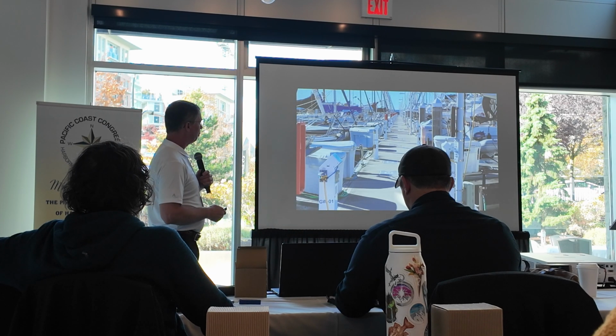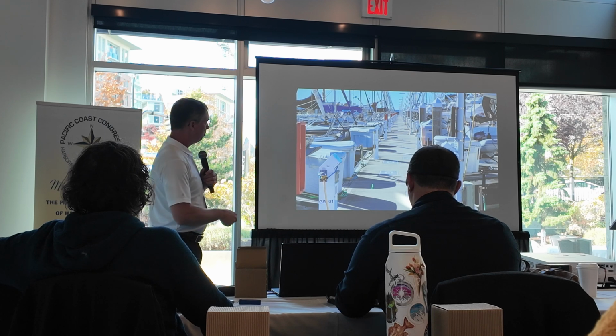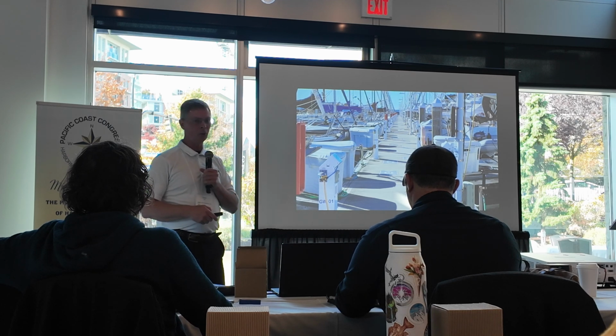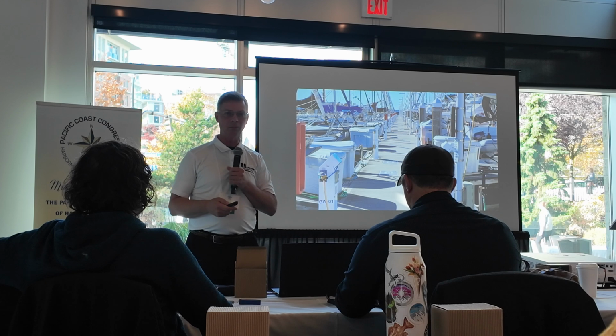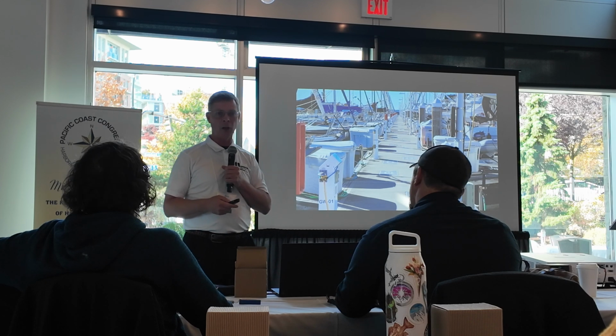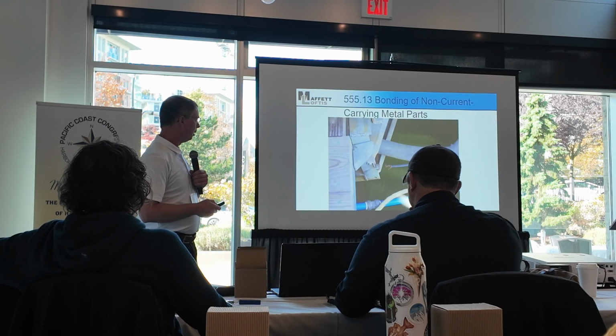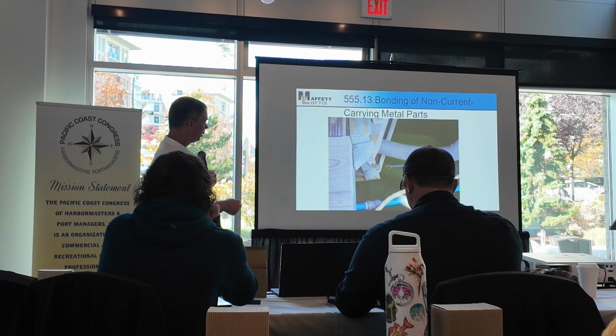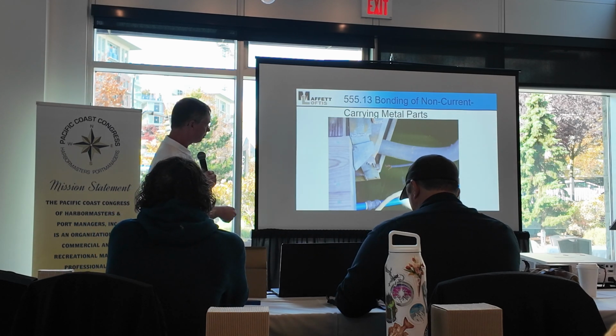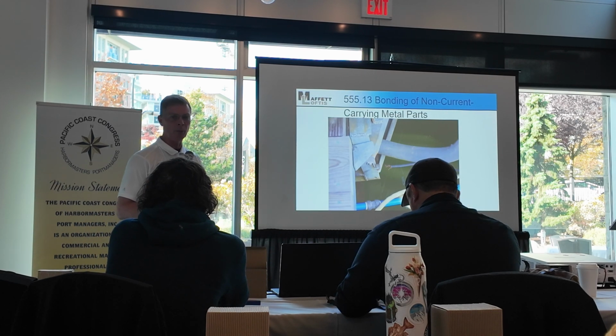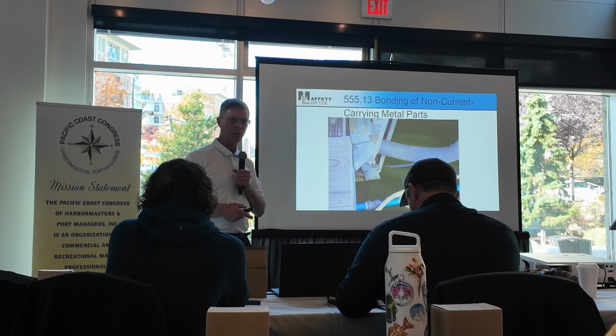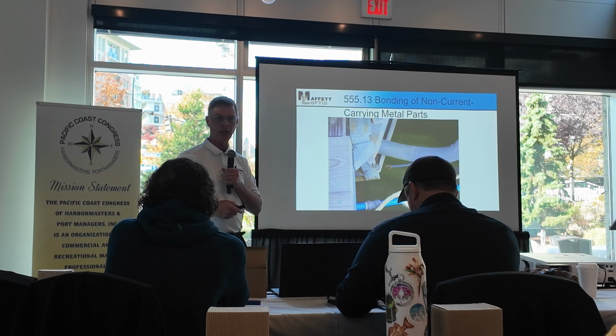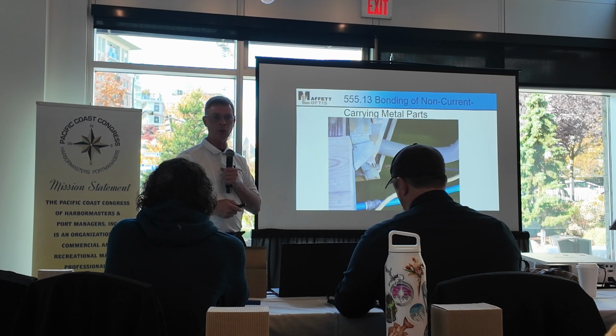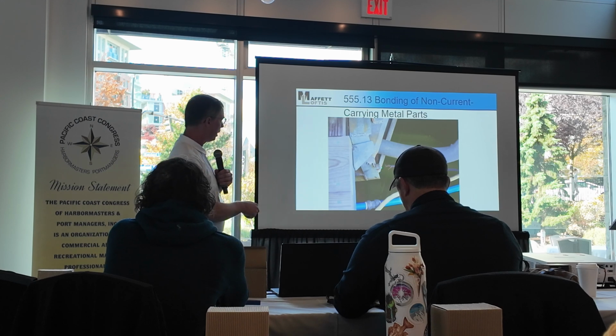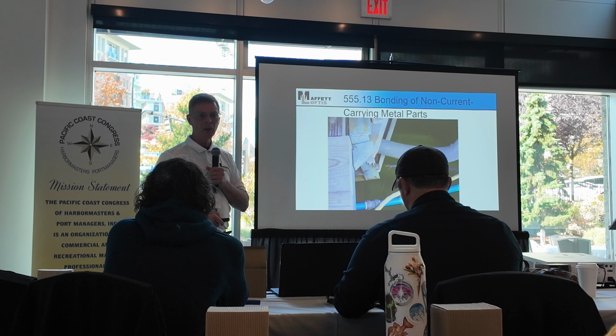I don't want to go through this, but if you're doing a dock walk, or in my case a performance testing, I see a lot of things. Remember the non-current-carrying metal parts, everything's supposed to be bonded. This is on a gangway bridge where you've got electrical cables coming down a bridge underneath on a gangway. That bridge is likely to be energized, so it's got to be bonded. But you've got a hinge point, in this case the fifth wheel, that moves all the time.